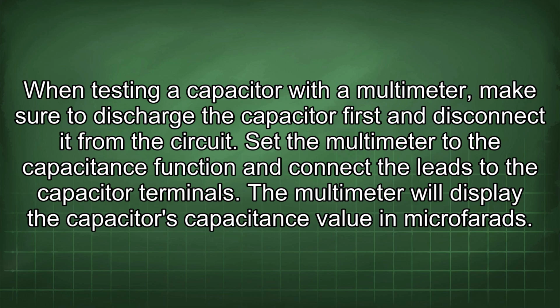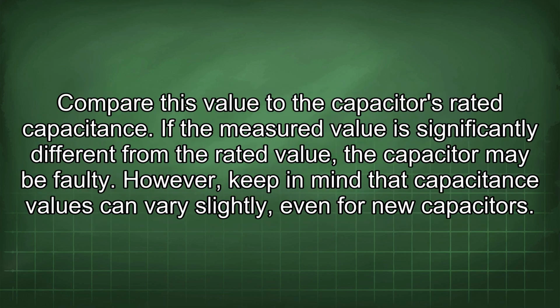Set the multimeter to the capacitance function and connect the leads to the capacitor terminals. The multimeter will display the capacitor's capacitance value in microfarads. Compare this value to the capacitor's rated capacitance. If the measured value is significantly different from the rated value, the capacitor may be faulty. However, keep in mind that capacitance values can vary slightly even for new capacitors.